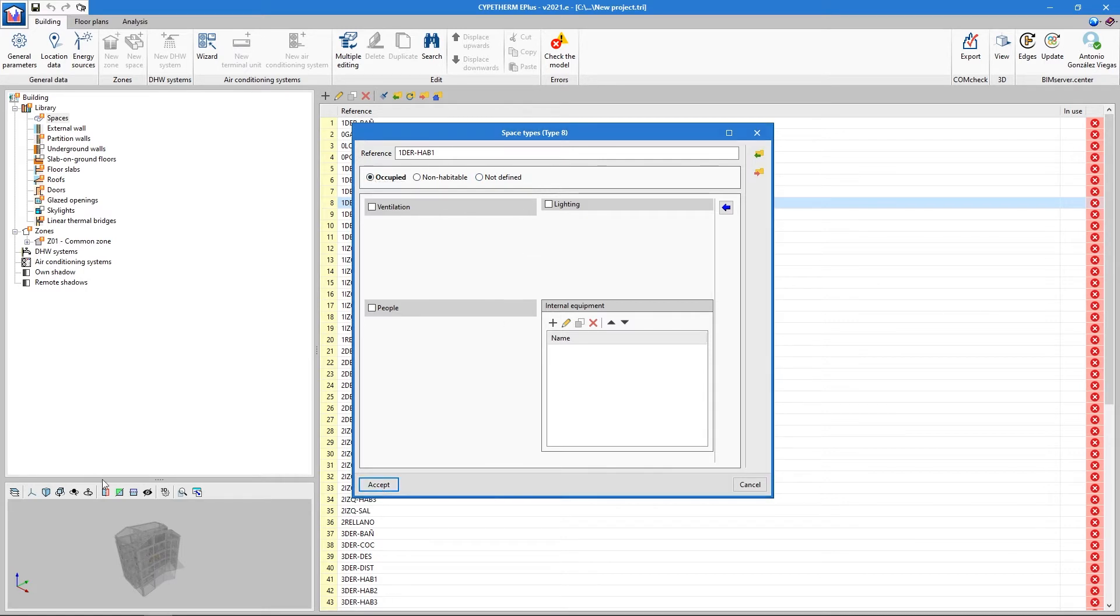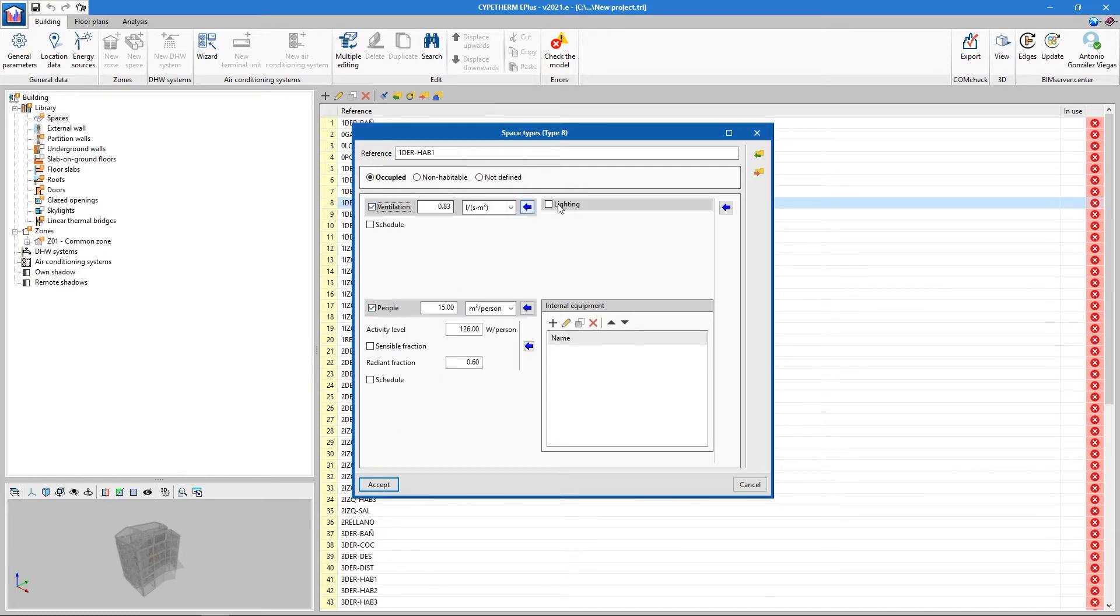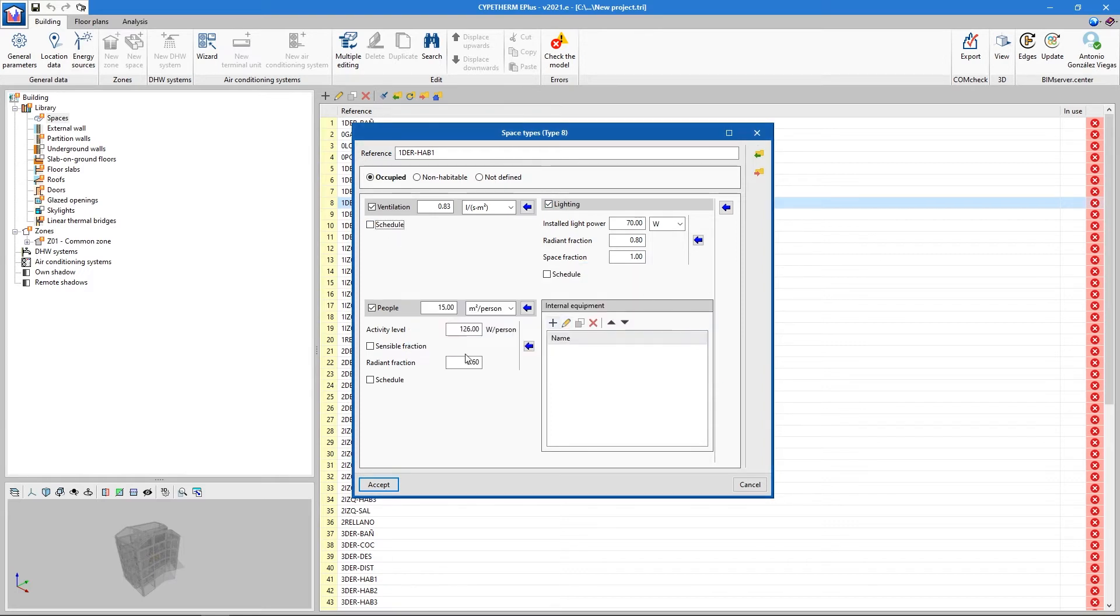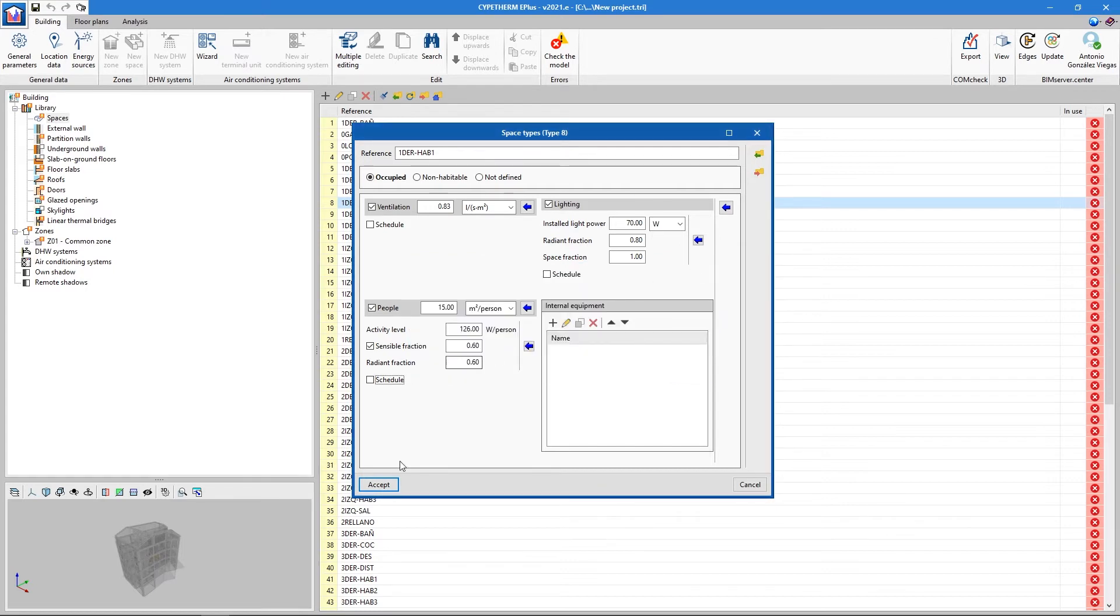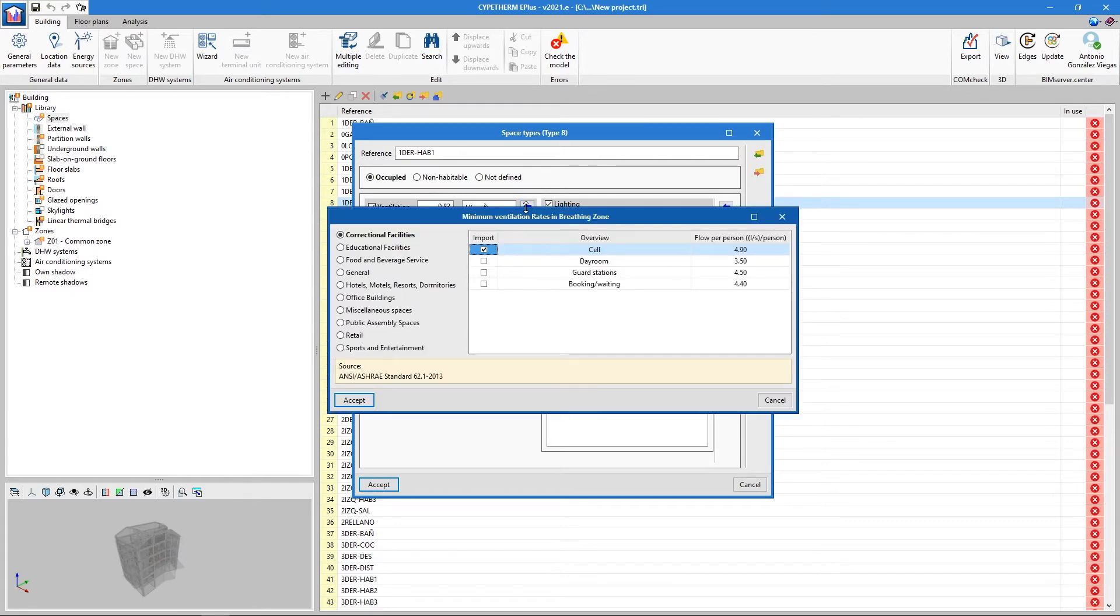In the list, we describe the energy properties of the space, including data for ventilation, lighting, people, and equipment. The more data we enter, the more precise the site thermal analysis will be. If we do not have all the information, we can use the automatic assistance by clicking on the blue arrow. It will allow us to automatically enter data according to the ASHRAE code criteria. For example, ventilation data can be entered automatically depending on the use of the building.